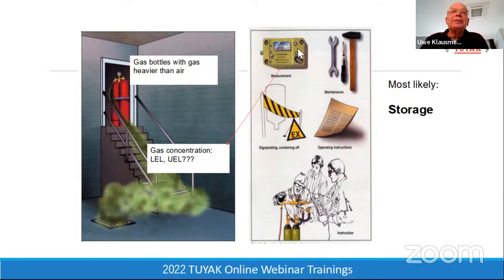And what you can do is measure the gas concentration, because we have a lower explosion limit and an upper explosion limit, which means we have an explosion range. As soon as the instrument measures that we are inside this explosion range, there has to be an alarm. As soon as we are under the lower limit, it's not ignitable. As soon as we are over the upper explosion limit, it's also not ignitable. Then we have to do the necessary maintenance. As soon as you have a distribution system, you have to maintain it. You have to sign such areas and rooms. You need operation instructions for the workers, and especially for the distribution system, you also need instructions for the using personnel.